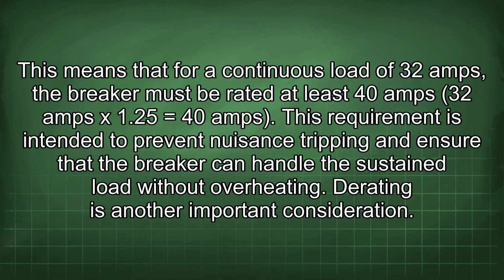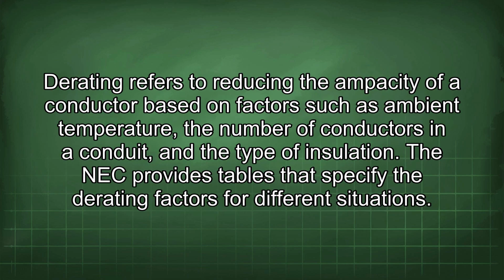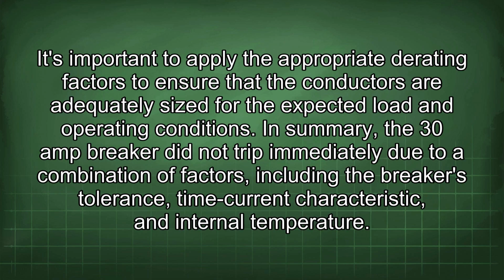Derating is another important consideration. Derating refers to reducing the ampacity of a conductor based on factors such as ambient temperature, the number of conductors in a conduit, and the type of insulation. The NEC provides tables that specify the derating factors for different situations. It's important to apply the appropriate derating factors to ensure that the conductors are adequately sized for the expected load and operating conditions. In summary, the 30 amp breaker did not trip immediately due to a combination of factors, including the breaker's tolerance, time current characteristic, and internal temperature.